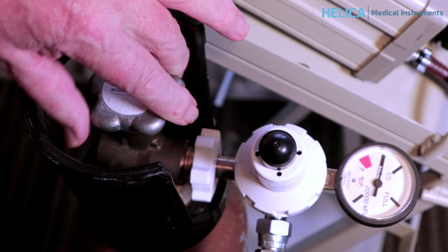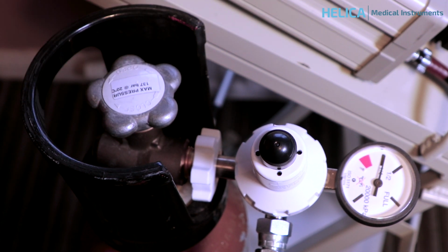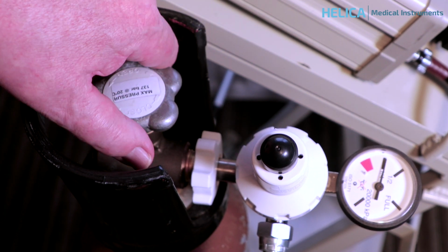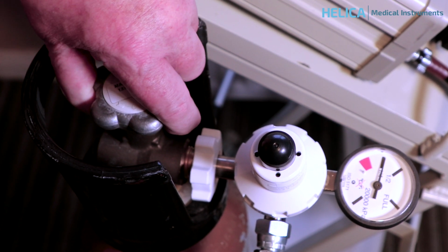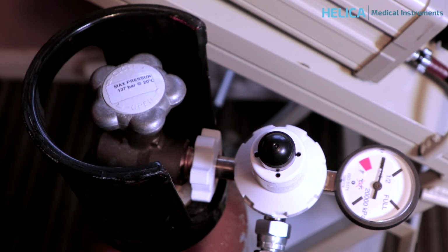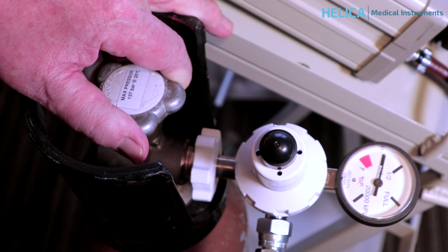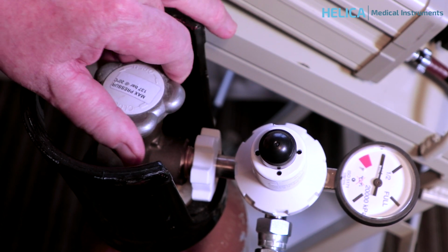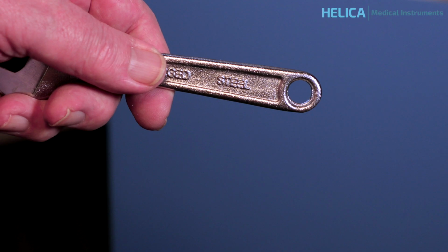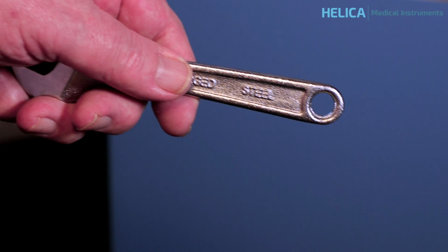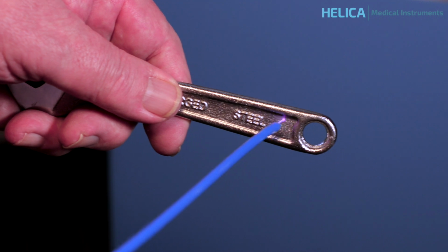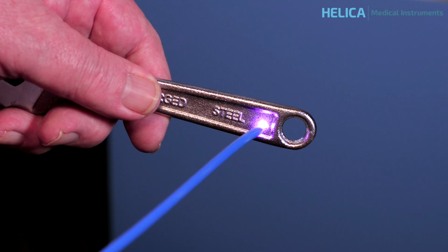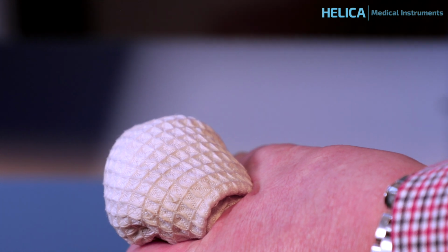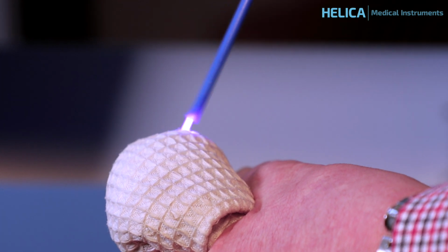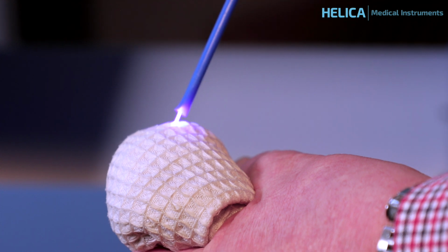Check the contents gauge to see if there's helium in the cylinder. Switch off the gas clockwise. If the gauge needle drops, this indicates there's a leak. If everything's okay, turn on the gas again. For convenience, we suggest testing each probe before use. This is done by pointing the probe to within 5 mm of any sterile stainless steel instrument, or a very wet swab, and then pressing the foot switch to check that the plasma beam can be clearly seen.